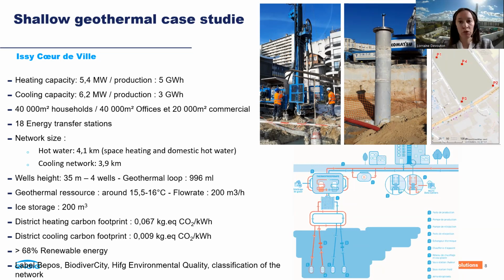And so, thanks to a big large-scale heat pump, as mentioned by Aurélie, we could benefit on one side of the heat pump from heating, and on the other side from cooling at the same time, which allows us to create sector integration and to use less electricity for the heat pumps running than if we had two separate systems. It also allows compliance with zero emission building regulation standards, or other standards we have in France, and we get a very low carbon footprint.